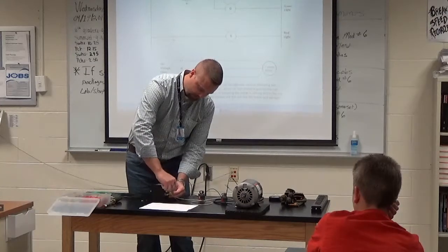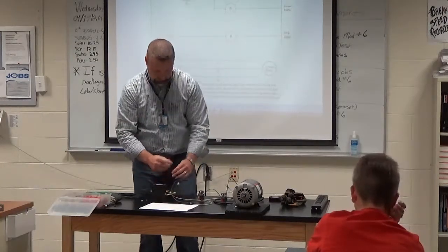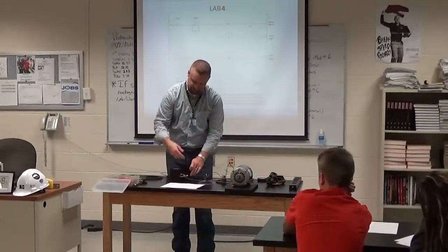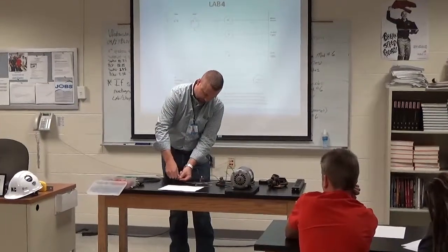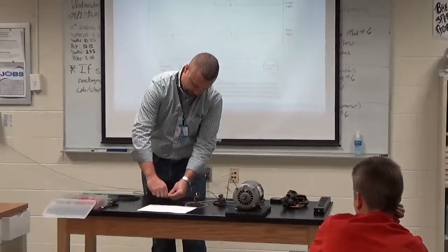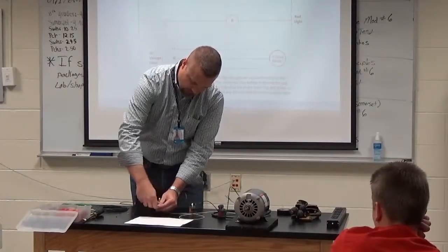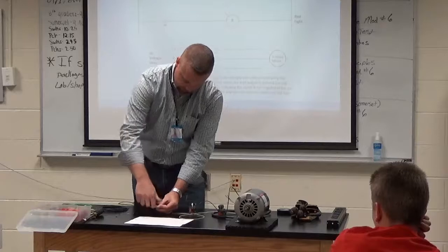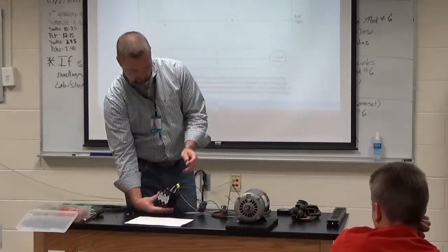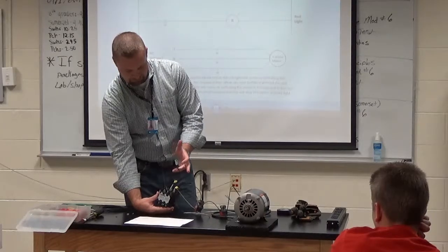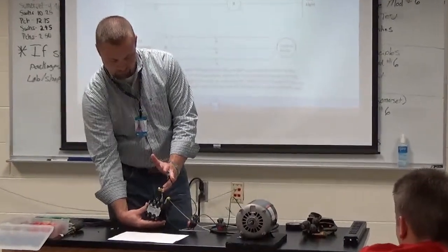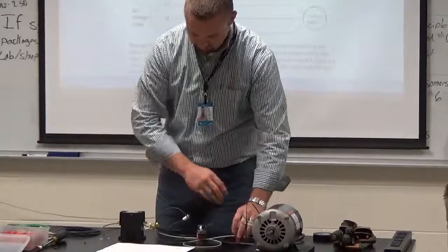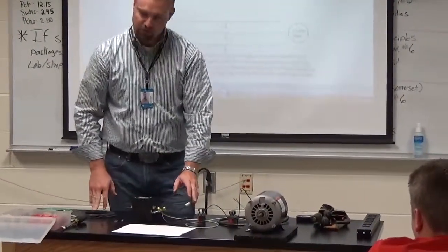Now, what's my next step, guys? Looking at your print. I've tied it into the coil going to the starter. What's my next step? Tie it into the neutral, right? It has to have a neutral to make that line operate. So I'm simply taking the cap off the neutral side of my starter and tying it with that. So basically, when you get done, this is what you should have, okay? You should have your green light connected with the coil on your motor starter. You should have that right there. So now what's going to happen is when I hit this start button, this motor starter is going to engage, this green light's going to come on, the motor will run.